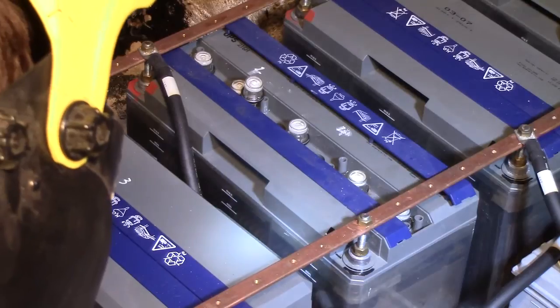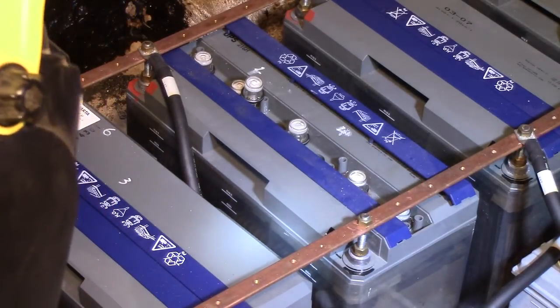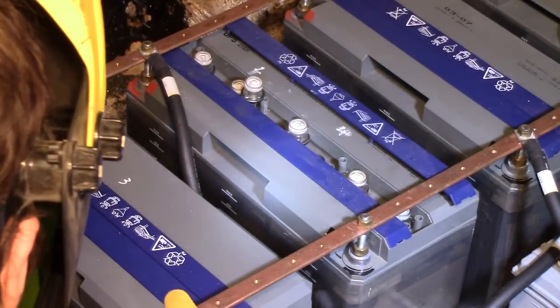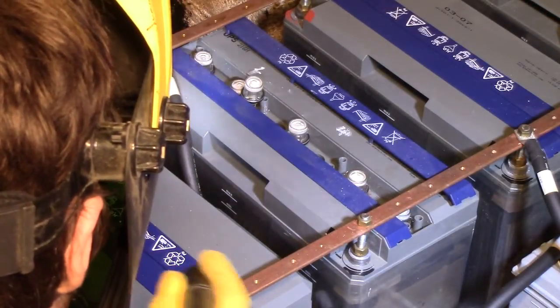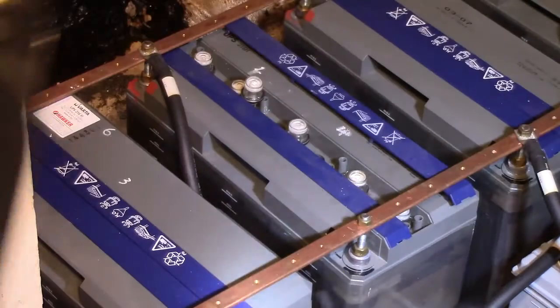I'm assuming it is a bubble. It could, of course, be a case of one of the other cells overflowing considerably and the electrolyte just seeping into that particular cell in case the cork had a bad seal. But that will have to be a case of study after I get the cell disconnected.